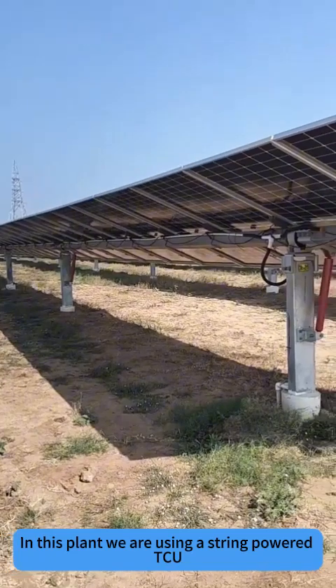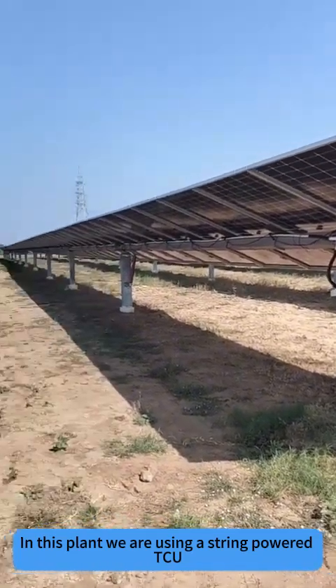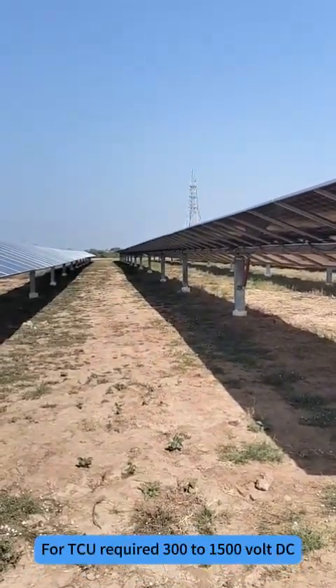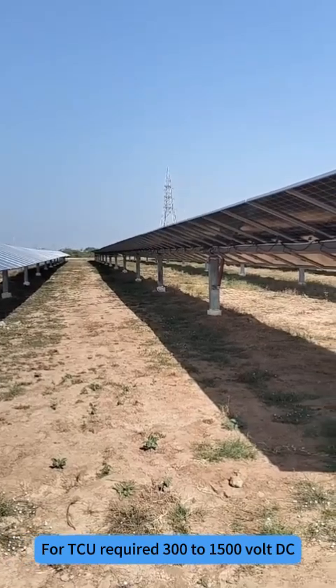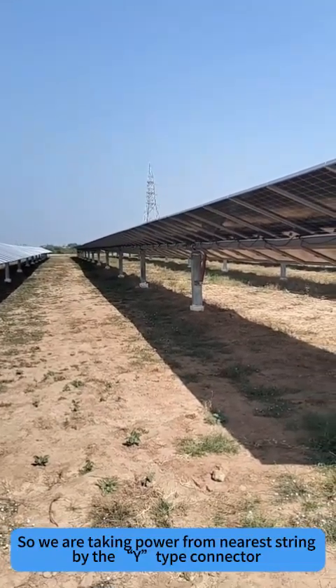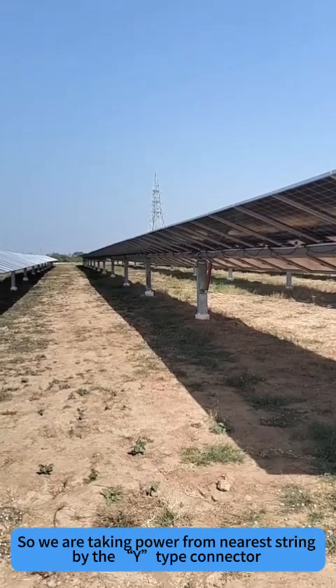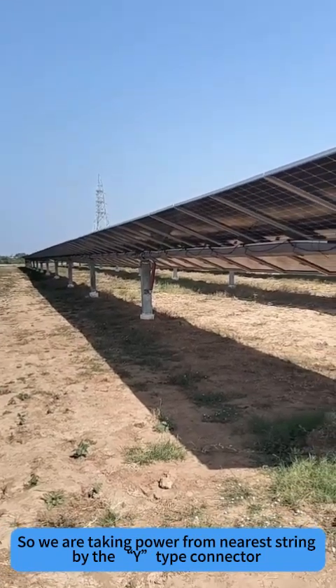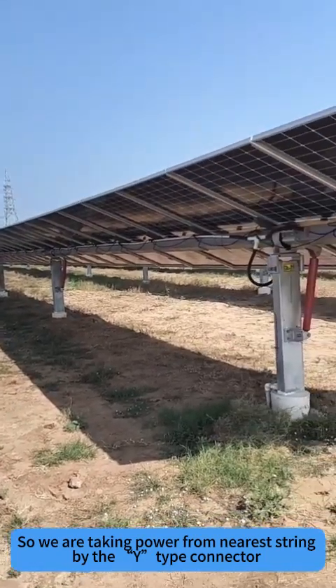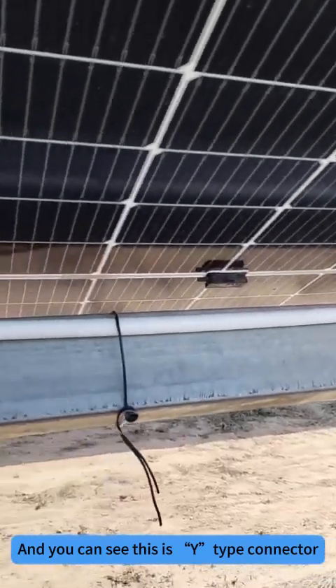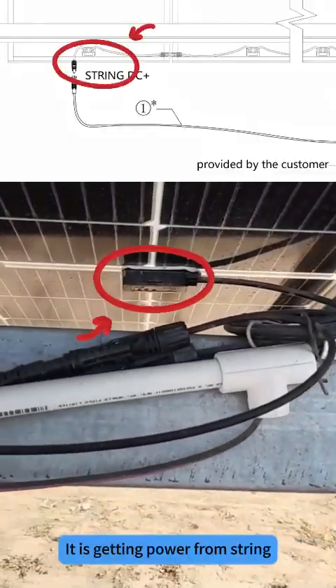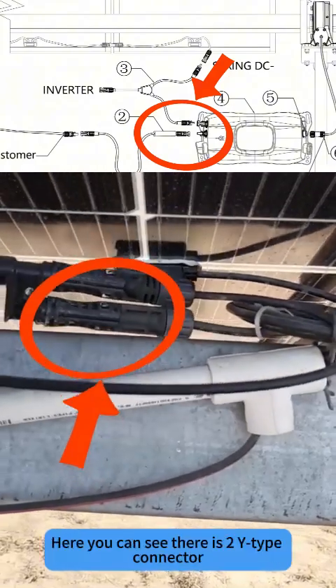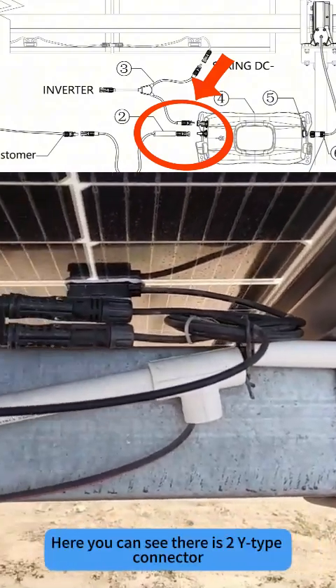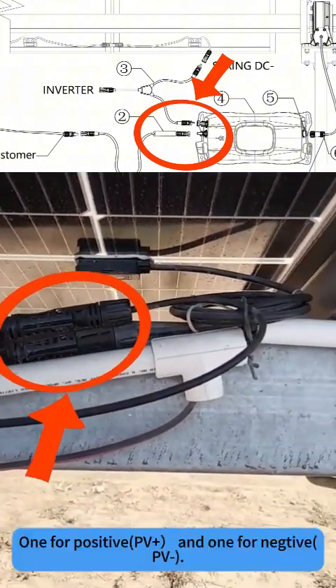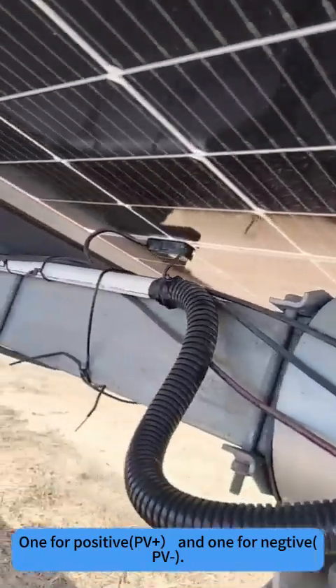Part 2. TCU strings power connection. In this plant we are using string power TCU. The TCU requires 300 to 1500 volt DC. So we are taking power from the nearest string by the Y type connector, and you can see this is the Y type connector. It is taking power from the string. Here you can see there are 2 Y type connectors, one for positive and one for negative.